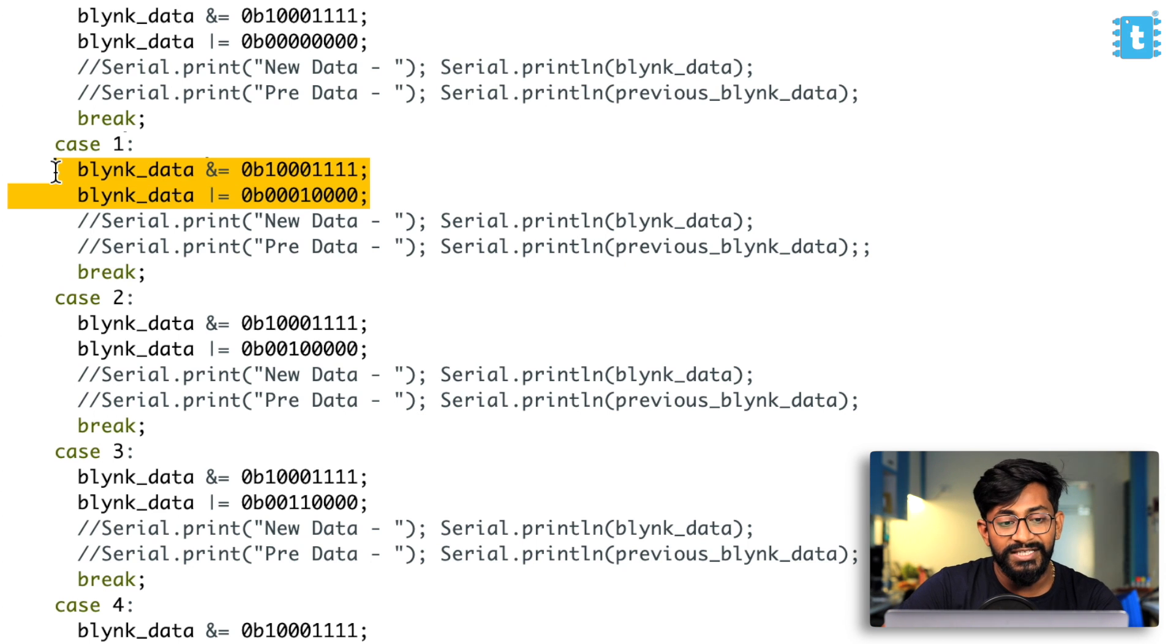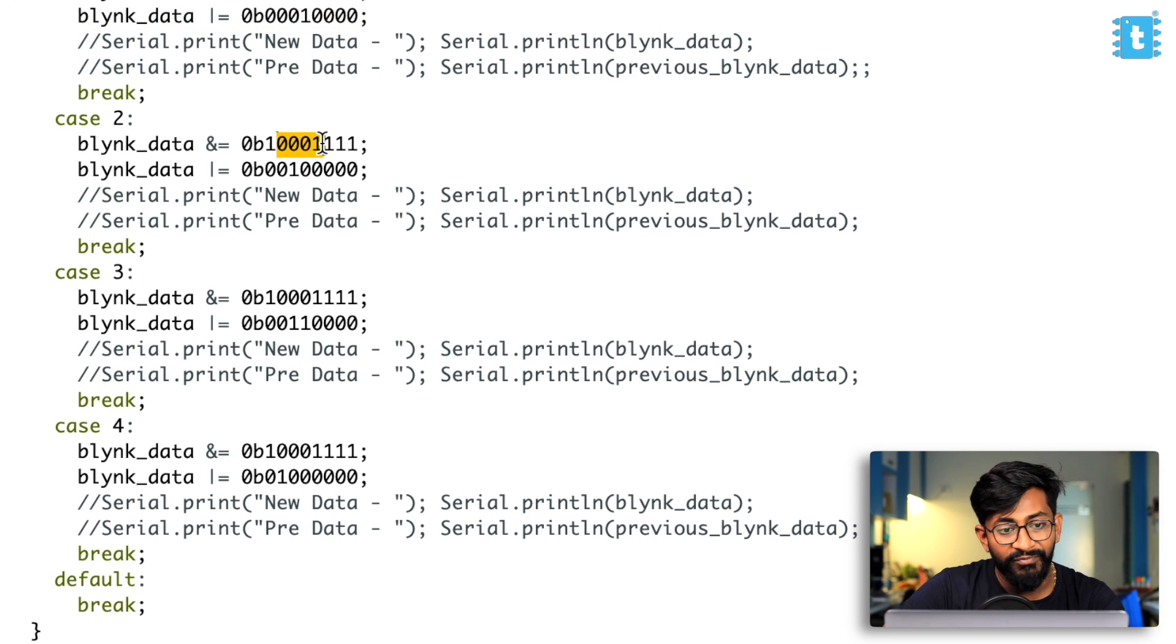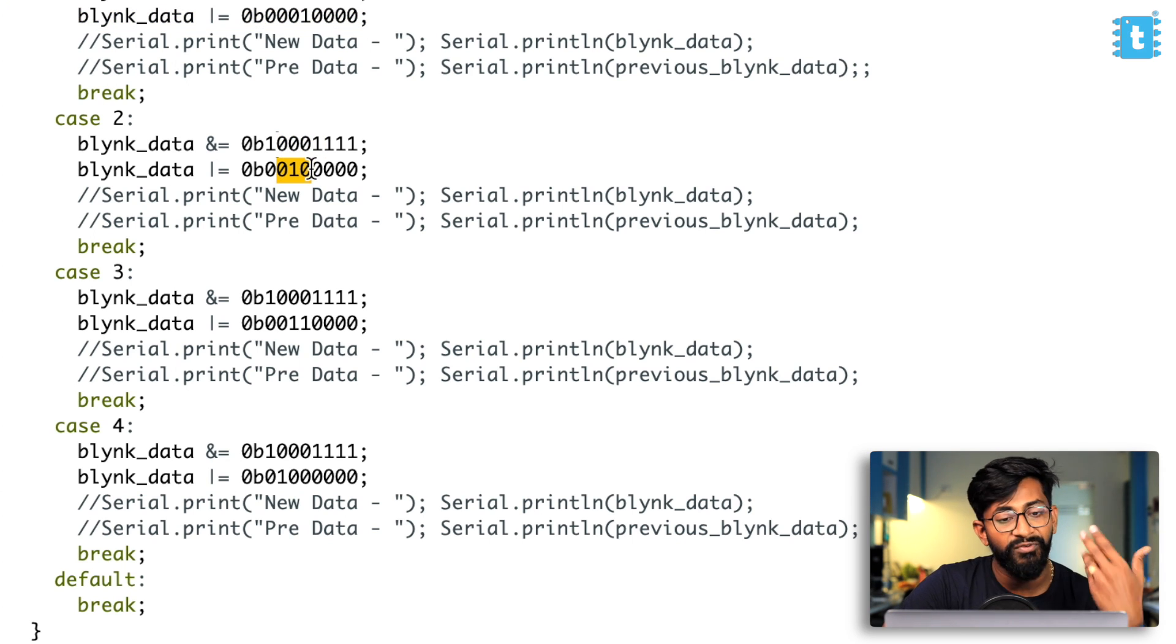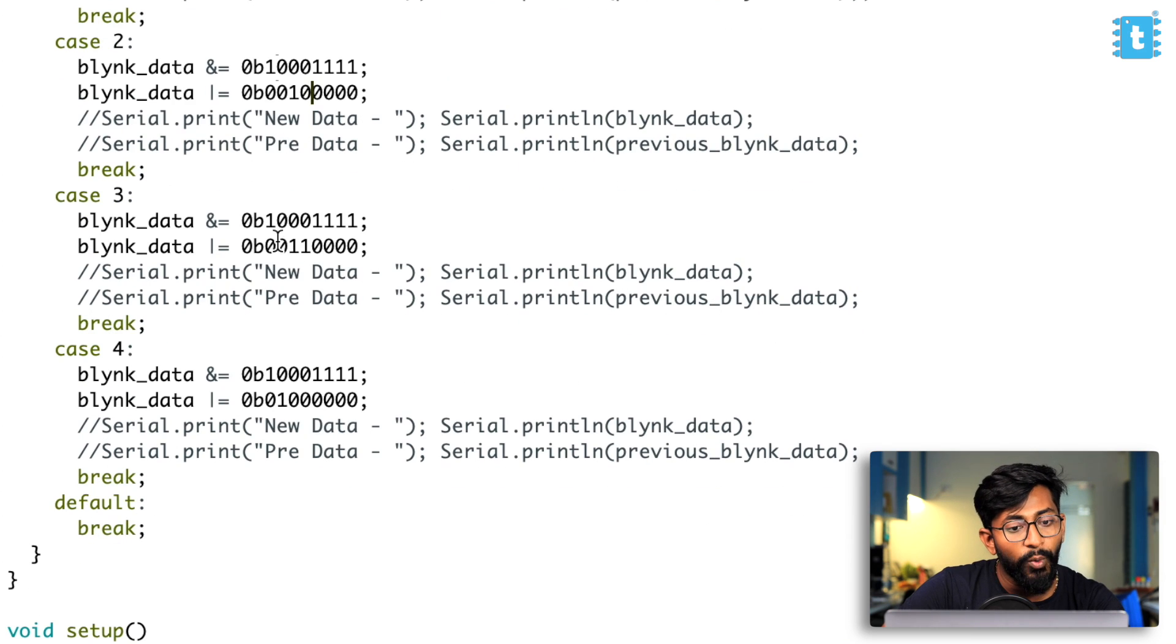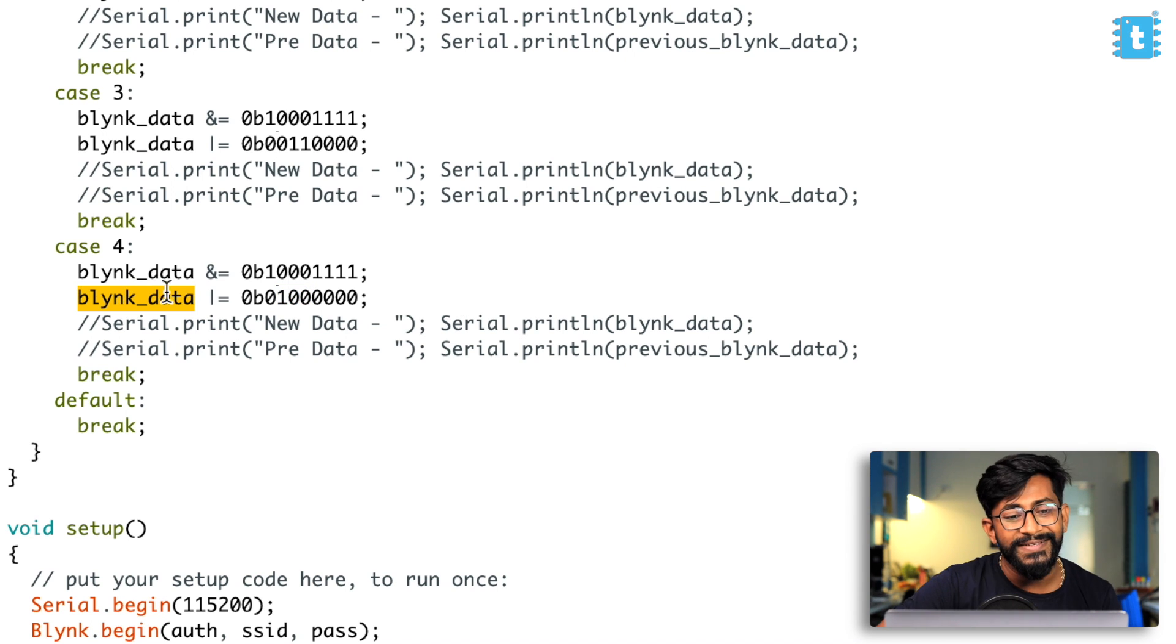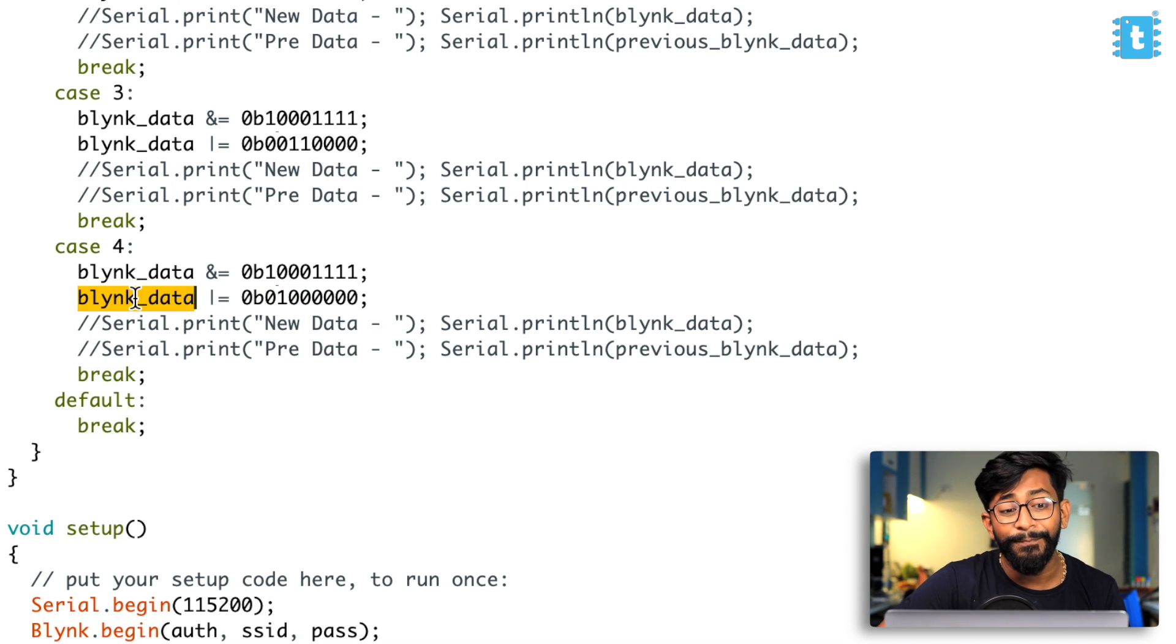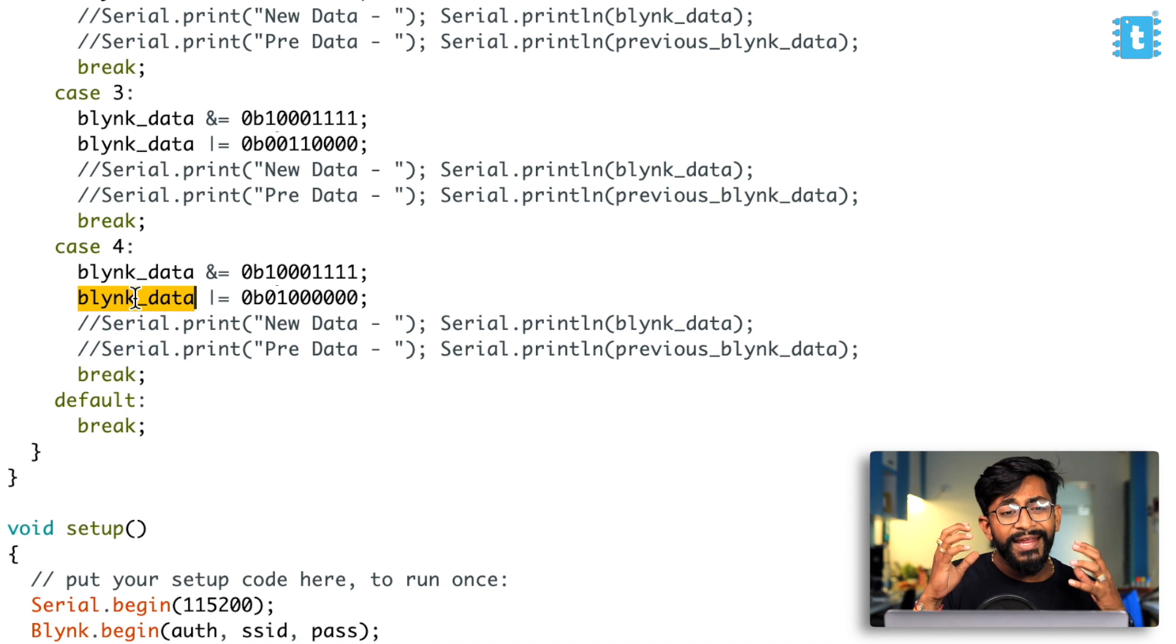So that's what we are doing here in case we receive the speed two, we are ANDing it with zero. First of all, after that, we are ORing it with zero one zero, which is for fan speed two, then zero one one, which is for fan speed three and one double zero, which is for fan speed four. So yeah, this is how we are storing all the data inside the blynk_data variable. But one thing is remaining, how we are sending this blynk_data variable to the actual relay.